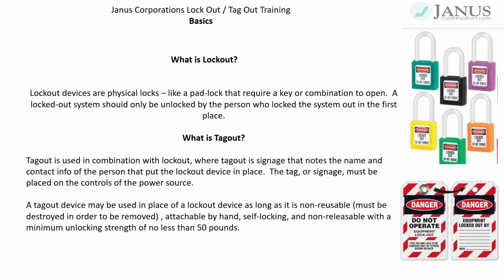Lockout devices are physical locks, like a padlock that require a key or a combination to open. A locked out system should only be unlocked by the person who locked the system in the first place. Tagout is used in combination with lockout, where tagout is signage that notes the name and contact information of the person that put the lockout device in place. The tag or signage must be placed on the controls of the power source.